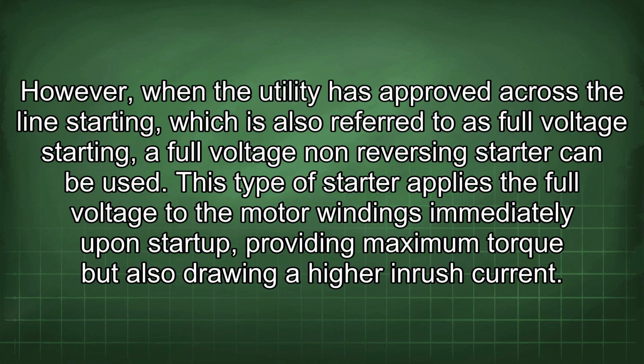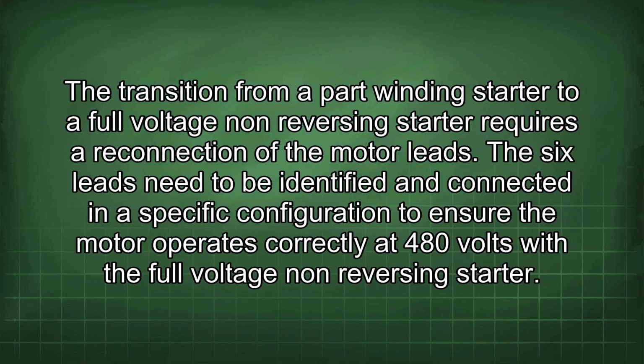This type of starter applies the full voltage to the motor windings immediately upon startup, providing maximum torque but also drawing a higher inrush current. The transition from a part winding starter to a full voltage non-reversing starter requires a reconnection of the motor leads. The 6 leads need to be identified and connected in a specific configuration to ensure the motor operates correctly at 480 volts with the full voltage non-reversing starter.